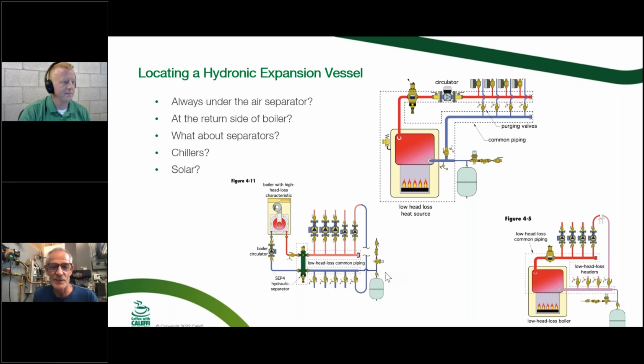So in all these pictures, we've got very low pressure drop between the circulator pumps, so they are all pumping away from the point of no pressure change, even though it looks like, gosh, it's a long way away from the circulator pumps on the left or on the bottom. But on the bottom, we've got a hydro separator in there, we've got large diameter piping. In the center picture, we've got a wide open boiler, cast iron, maybe an electric boiler, whatever it might be, with very little pressure drop in that boiler. So they could be on that bottom side there.